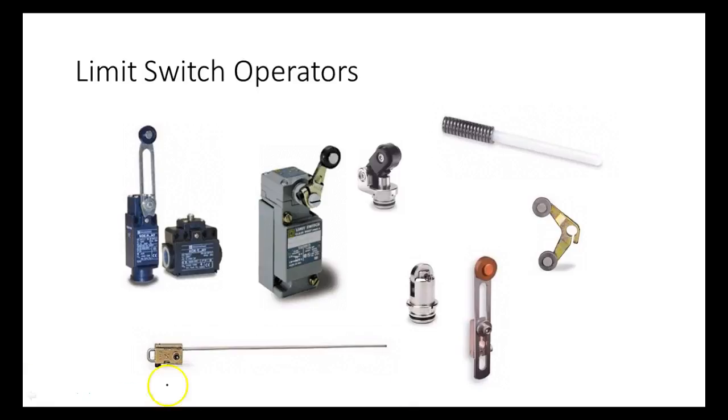Now, what would you think is the biggest problem we have with these guys? Sticking, and people that adjust them wrong, right? They'll put them in there, get them too close, and knock the operator off, break the operator off, or they get too far away. And they're electromechanical devices, which means what? Two ways to fail. They can fail electrically, and they can fail what? Mechanically. But for what they do, they are probably the least expensive, the most cost-effective that you'll run into. They're a lot cheaper than solid-state sensors.